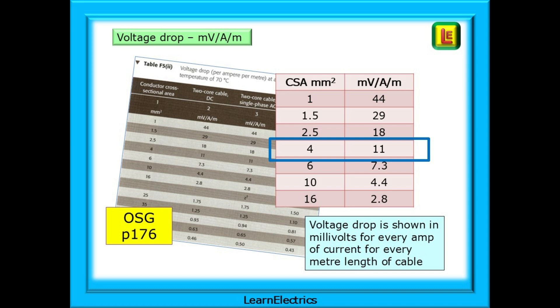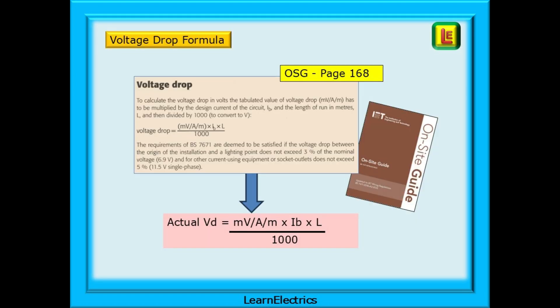Page 176 shows a variety of voltage drops, and we are interested in single phase AC voltages, with the values shown in the pink table. Page 168 of the on-site guide shows the formula that we should use in order to calculate the actual voltage drop in the cable. Note that we only measure the length in one direction, from the consumer unit to the load, and not there and back. The actual voltage drop, or VD, is equal to the millivolts per amp per metre, multiplied by the load IB, multiplied by the length in metres. This is all divided by 1000 to convert the answer into volts.